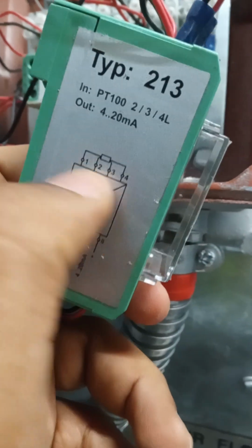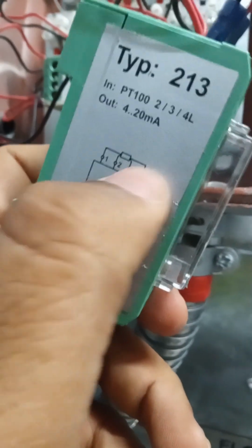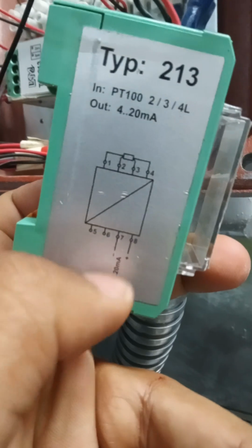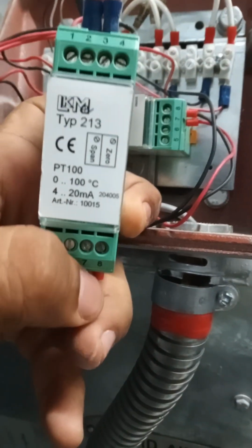Whatever cable is coming from the field has to connect at 2 and 3. I mean, these two cables have to connect at 2 and 3, and 1 and 2, and 3 and 4 are shorted. This 7 and 8 is the 4 to 20 milliamps output. So you can see 7 and 8 here. This is the 4 to 20 milliamps output.